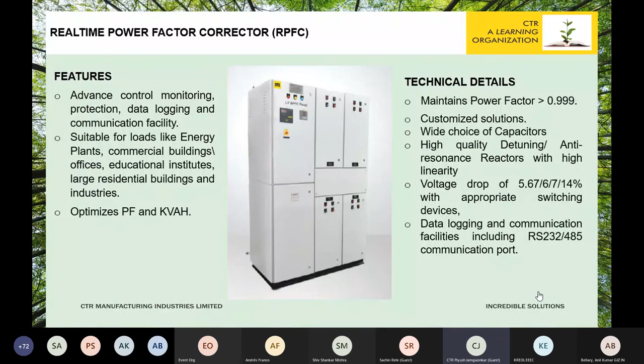So we have a wide range of capacitors available, the heavy duty, the super heavy duty, oil impregnated, the anti-resonance reactors, and with a high linearity and wide range of voltage drop up to 14%. With appropriate switching devices and advanced control monitoring and protection features, apart from data logging and communication facilities, including the RS-232 and RS-485 communication port. These are available from single unit 10 kVAR to 1000 kVAR and 1 to 16 stages.